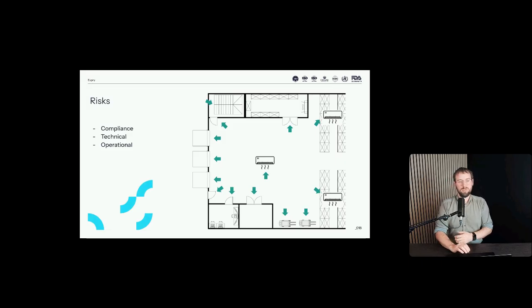So just taking this as an example, we know that there are risks associated with doors and gates both during summer and winter mapping. So we should place sensors there. We know that there are risks associated with the temperature control system, so we should place sensors there. We might have operational risks. So where do we load products into the facility, and where do we unload them again, and where are they placed in the meantime until they get to shelving?